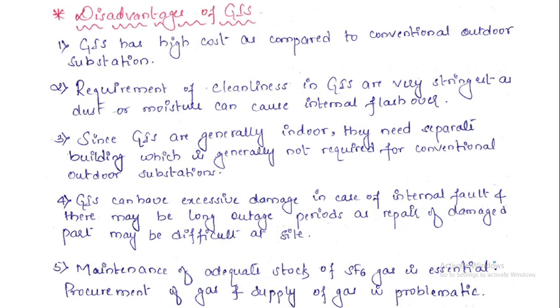Requirements of cleanliness in GIS are very stringent, as dust or moisture can cause an internal flashover. As we are using GIS indoors, the area where the GIS system is installed should be very clean. It should be dust as well as moisture free.